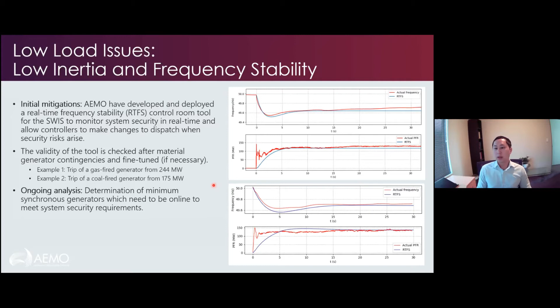In terms of ongoing analysis, we're working out the minimum number of generators that need to be online to meet system security requirements. As system loads get lower, we need to think about minimum synchronous machine floors, or inertia floors. We haven't hit them yet, but studies are ongoing, and it's quite possible that frequency stability isn't the main driver for these floors—it could be something like system strength. But we haven't quite got there yet.